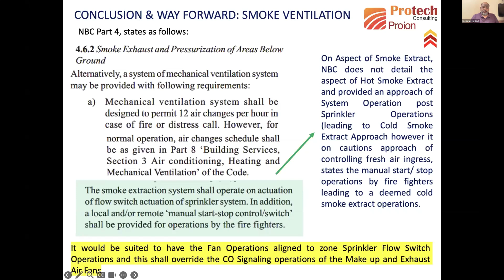If you look at the National Building Code of India, it clearly says in the green box, local and remote manual start-stop switches are required. That means automation of a smoke management system is, honestly speaking, highly undesirable. If you try to automate too much of the smoke management system, you only end up covering situations where automation works. But in smoke control management scenarios, a lot has to be dealt with by firefighters through manual overriding provisions. So automation is not very effective for smoke management. It has to have manual controls, as written clearly under NFPA item number 3 on the right: activation by manual operations.